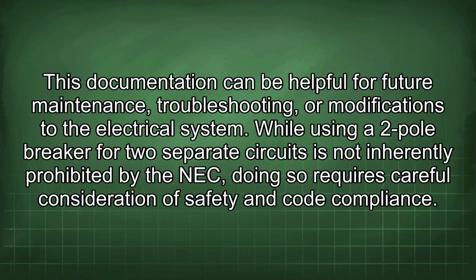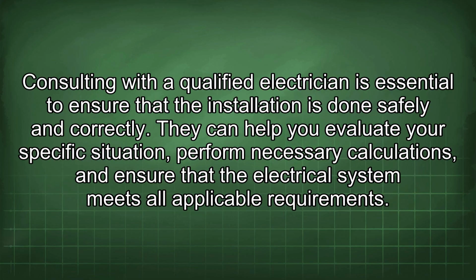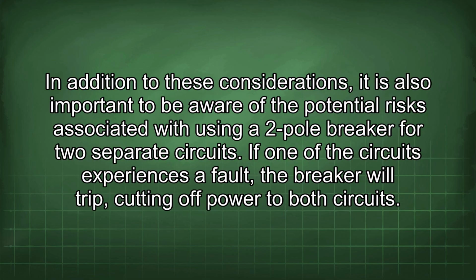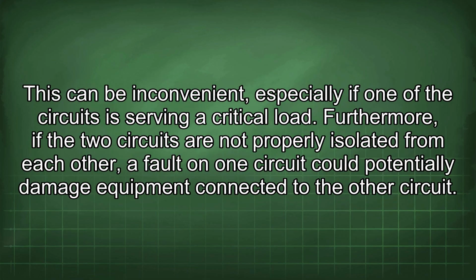While using a two-pole breaker for two separate circuits is not inherently prohibited by the NEC, doing so requires careful consideration of safety and code compliance. Consulting with a qualified electrician is essential to ensure that the installation is done safely and correctly. They can help you evaluate your specific situation, perform necessary calculations, and ensure that the electrical system meets all applicable requirements. In addition to these considerations, it is also important to be aware of the potential risks associated with using a two-pole breaker for two separate circuits. If one of the circuits experiences a fault, the breaker will trip, cutting off power to both circuits. This can be inconvenient, especially if one of the circuits is serving a critical load.